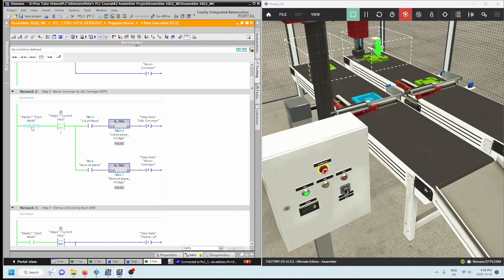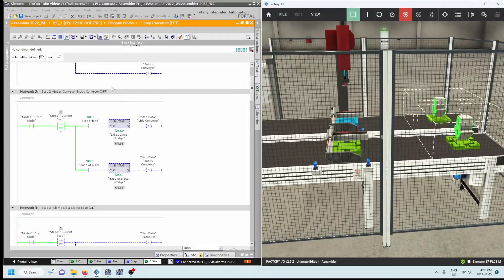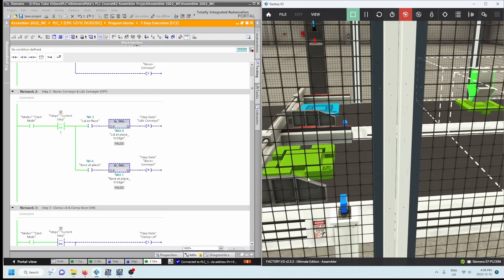Step two: start mode is true, current step equals two, and we have 'lid at place' and 'base at place' — this sensor and this sensor. We discussed in the previous video that we want the negative edge: it goes from zero to one and then back down to zero. We're looking for the N-trig — the negative trigger — for each of these. Make sure to use separate memory bits for each one. At that point we reset each of those conveyors.